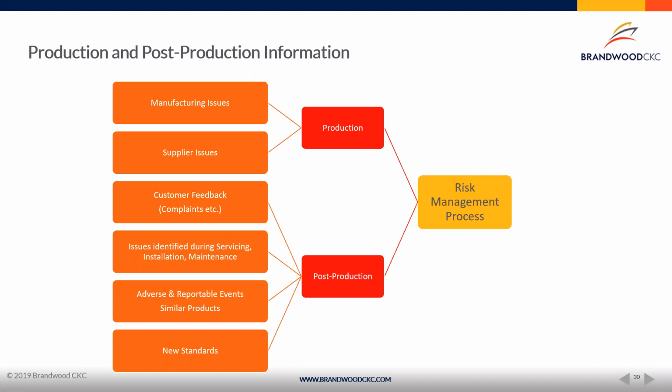For devices that require servicing, installation, or maintenance, your staff that's in the field will be a great source of information about the suitability of the device. And when that comes back to you, again, you put it back into the risk management process so you can go through those steps. You can identify whether that is a new harm or hazard that's been created, or not previously identified, or whether you just have something that wasn't identified correctly from a probability and severity perspective. Then going through the process and identifying whether controls are necessary, or what needs to be done to make that an acceptable risk.